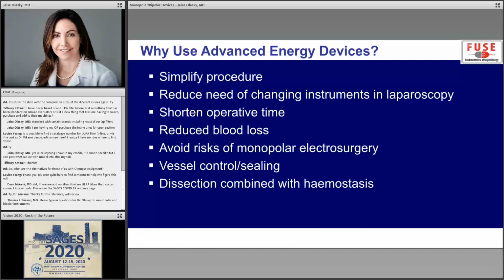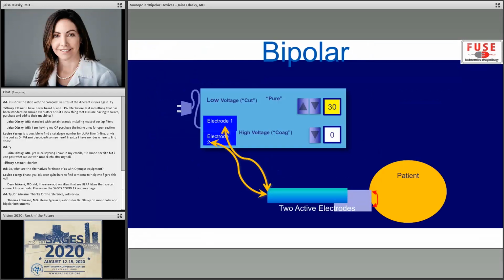They're really good for vessel control and sealing, and they're also good for dissection. A lot of them, you can get ones with the Maryland tip and dissect with it as well. So again, shorter OR time, fewer instrument changes. The bipolar devices do have the two active electrodes near the tip of the instrument, so you're not going to have to worry about energy going into other parts of the patient.